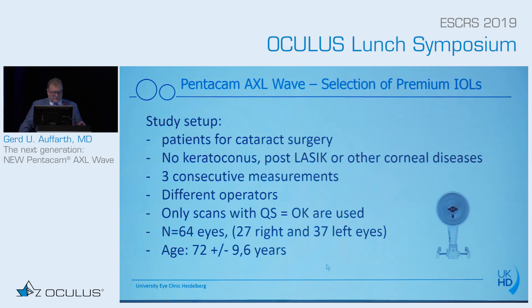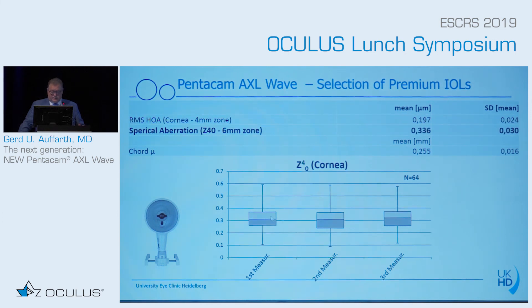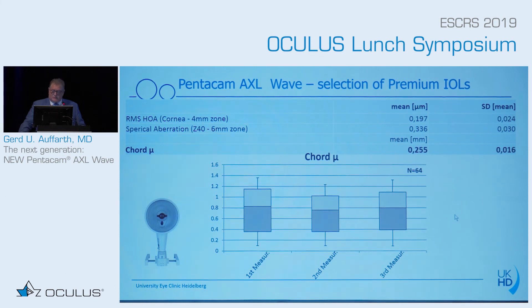64 eyes have been collected so far. Both studies are interim, so we are increasing the numbers as we continue. Looking at high-order aberrations at the cornea 4 mm zone, you see the mean and standard deviation with almost identical first, second, and third measurements — very good repeatability. The spherical aberration similarly shows a normal standard deviation and very similar consecutive measurements. This also applies to Chord Mu, with just a little variation between measurements.